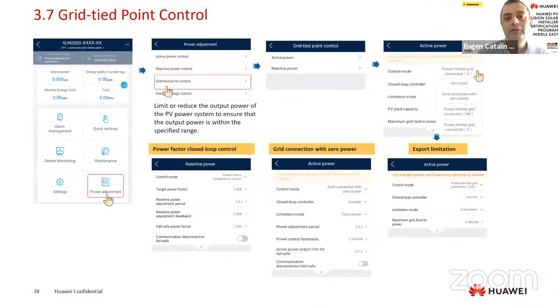We have grid-tied point control in active power. This is a variable control. What does this mean? Using the smart power sensor is mandatory to act in grid-tied point control. I can set the inverter in grid connected with zero power. This means that the power sensor will measure the consumption, of course, and send the information to the inverter, and the inverter will act.